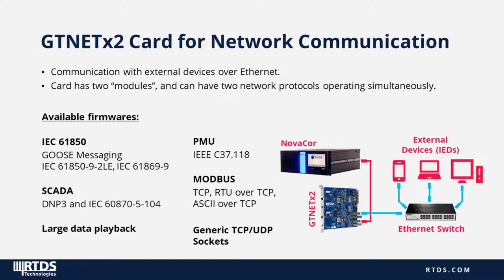Our communication-based I/O card is called the GTNet X2, and this card facilitates bi-directional communication between the simulation and external devices via Ethernet. The card has two processors which we call modules, and each module can run a network protocol in parallel, so the card can have two network protocols operating simultaneously. In addition to IEC 61850 GOOSE messaging, it is also capable of sampled values simulation, SCADA protocols DNP3 and IEC 60870-5-104, Comtrade or ASCII playback, PMU protocol, Modbus, and generic TCP and UDP socket communication.